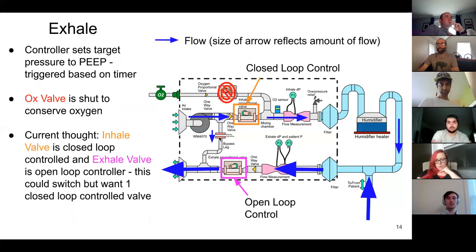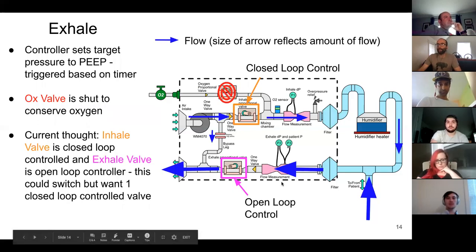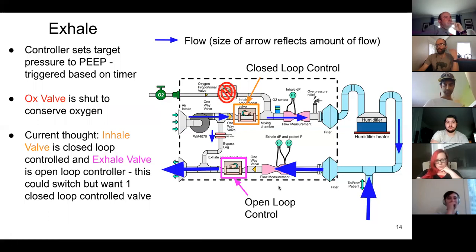Okay, so then it's time to exhale. When it's time to exhale, we're going to close the oxygen valve. We don't need to be wasting any oxygen during exhale. And then we're going to open the exhale valve. We might not open it all the way, right? We might not just treat it like a solenoid and jump it to full open. We might jump it to full open and then ramp it slowly closed as we assume the patient's exhaling.